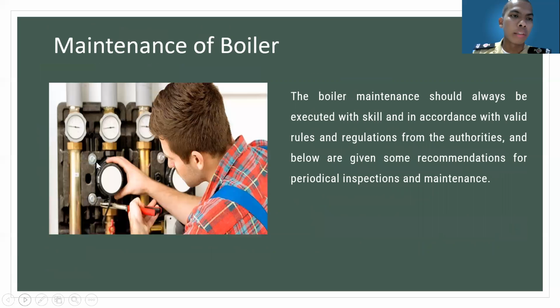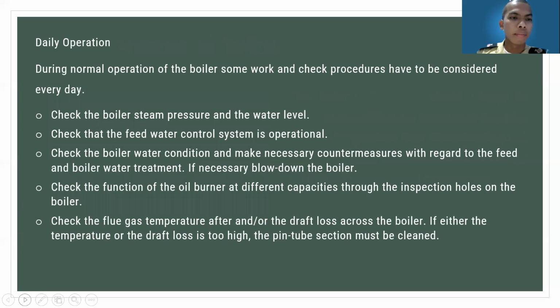So we will take a look at the maintenance of boilers. Boiler maintenance should always be executed with skill and in accordance with valid rules and regulations from the authorities, and below are given some recommendations for periodical inspection and maintenance. So in daily operation, during normal operation of the boiler, some work and check procedures have to be considered every day. Firstly, we need to check the boiler steam pressure and the water level. And also we need to check that the feed water control system is operational. And also check the boiler water condition and take necessary countermeasures with regard to the feed and boiler water treatments, and blow down the boiler if necessary.